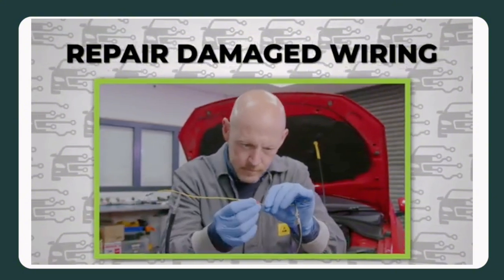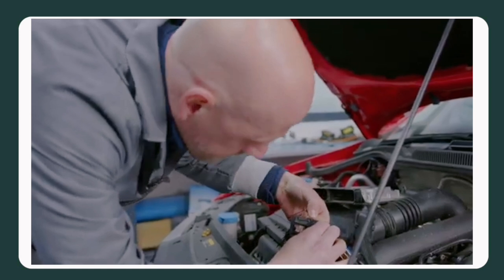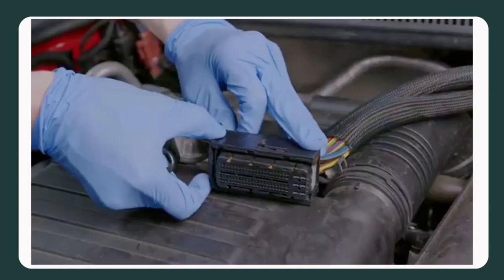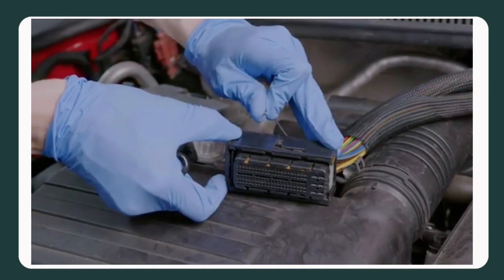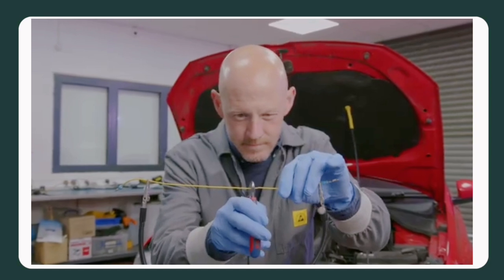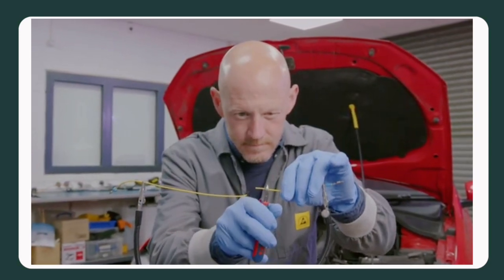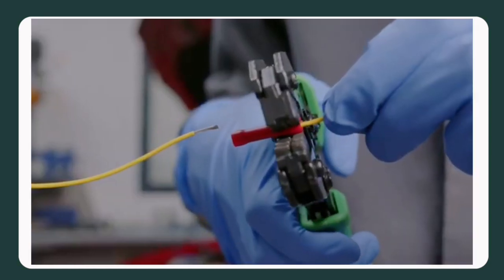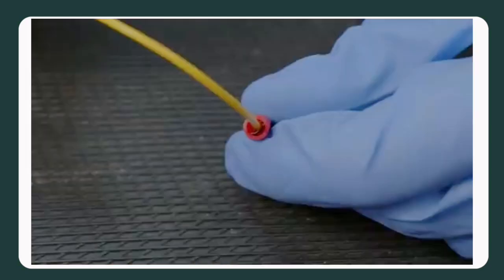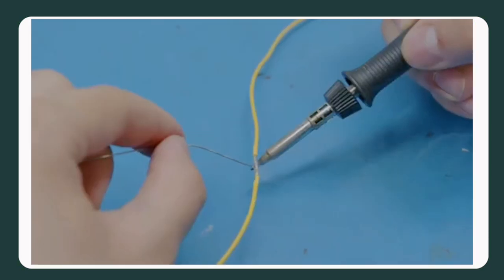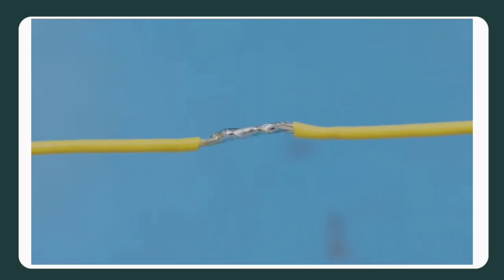Now you know how to back probe and find a fault in your wiring, but how do you fix it? Well, here you have a few options. You can either completely remove and replace a damaged wire if access is easy enough, or cut out the damaged section of wiring. Bear in mind that every time you cut and rejoin a wire, you're creating a potential point of weakness for ingress to enter. So ensuring you are properly repairing any damage is pivotal.